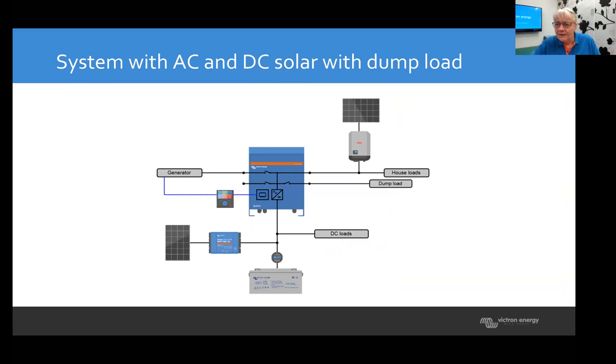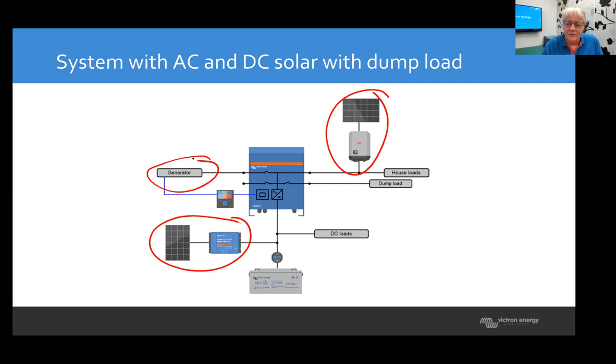Example of a system like this: you've got your AC inverter here, you've got your DC here, and basically that's what you can match a generator to. That's not a problem at all. The generator usually does not run when AC is running, or it only runs when the batteries are empty, and then it doesn't matter who charges the battery. Sometimes people are afraid that AC will start feeding into the generator, but that doesn't happen because that's when the generator is not on.